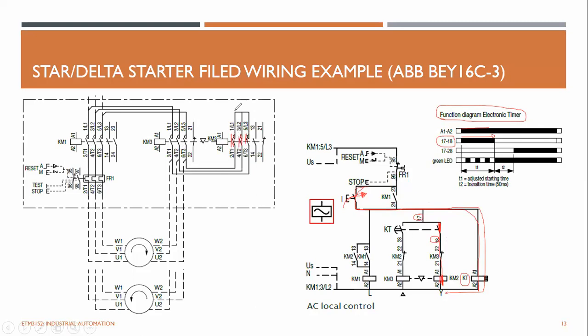So you can see now it short circuits the three terminals, and the motor runs with the star connection. The motor runs with the star connection initially, 17 and 18 closed, and the KM2 coil is energized. At the same time, we can see KM2 is running. This is opened.